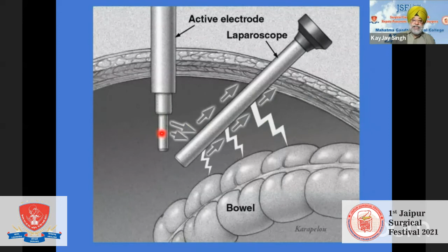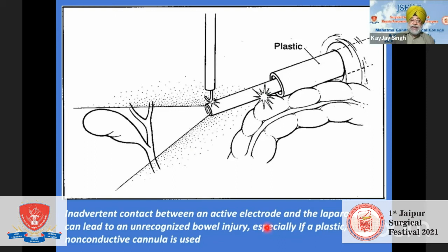Now, this is what is called direct coupling. You see here the electrode delivering the energy from the electrosurgical unit is in very close proximity, or in fact, even at times it may touch the telescope, the metallic part of the telescope. And in that situation, any bowel or any organ that is coming in contact with the telescope is going to sustain injury. Inadvertent contact between an active electrode and the laparoscope can lead to an unrecognized bowel injury, especially if a plastic non-conductive cannula is used. This is very important. I'll build up a case of why plastic is not the ideal conductor from this aspect of consideration.